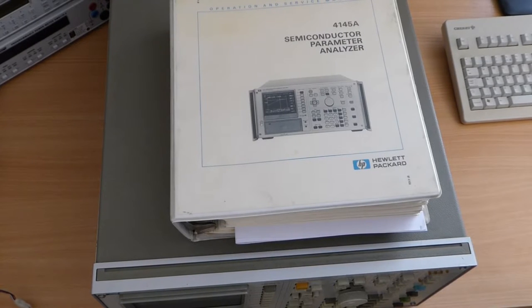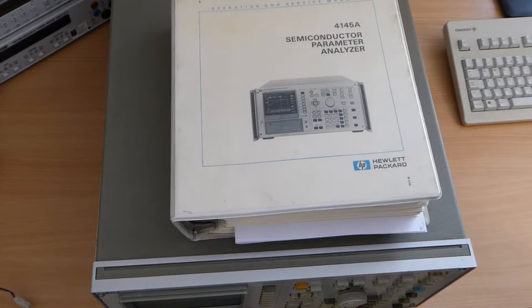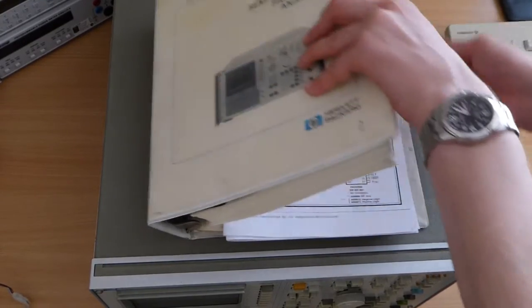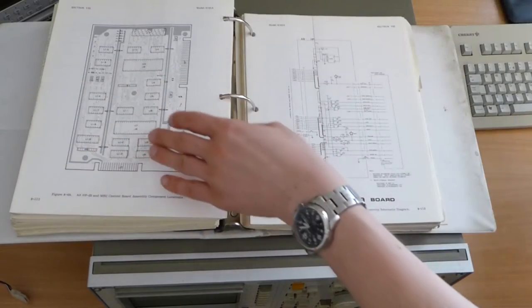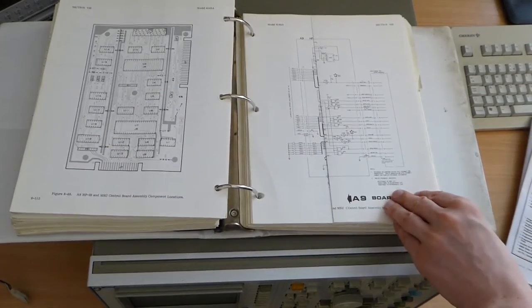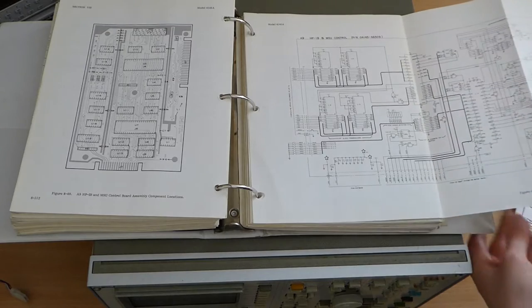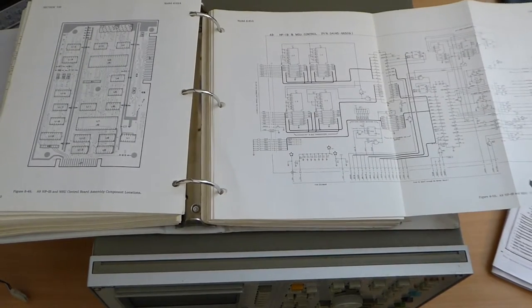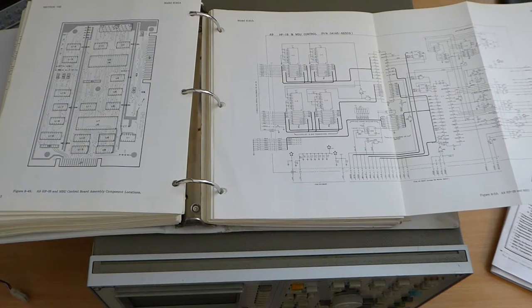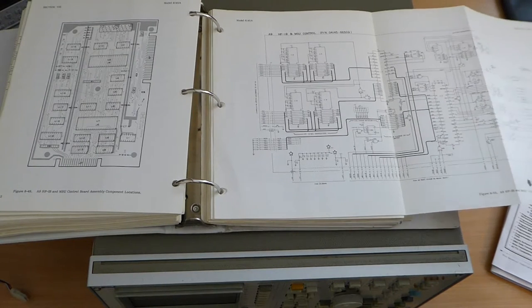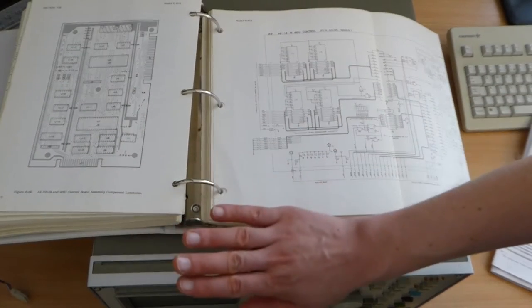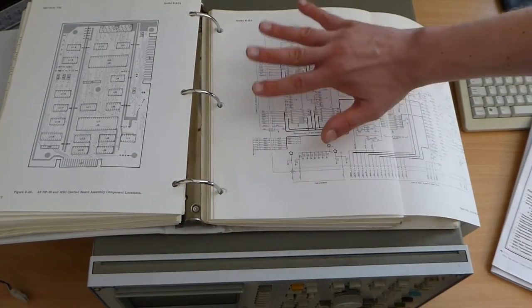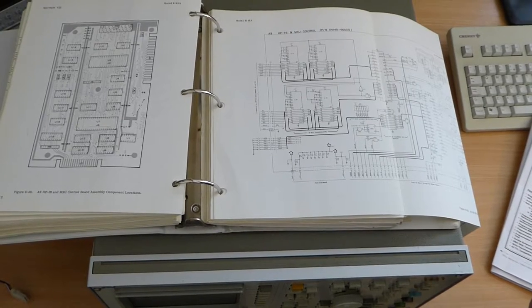The starting point for this is obviously the service manual. I've got the original copy here but you can download a PDF from Keysight so they keep that around. And on here we have the floppy controller. And it turns out that the entire floppy disk controller is actually on a separate board together with the HPIB connector. So in theory it should be possible to just remove this entire board from the analyzer and interface to it somehow to read off the floppy disk.